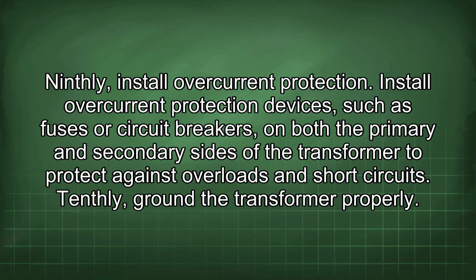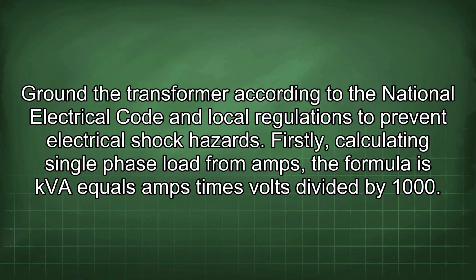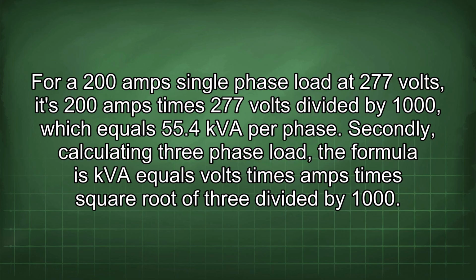Tenthly, ground the transformer properly. Ground the transformer according to the National Electrical Code and local regulations to prevent electrical shock hazards. Firstly, calculating single-phase load from amps. The formula is kVA equals amps times volts divided by 1000. For a 200 amp single-phase load at 277 volts, it is 200 amps times 277 volts divided by 1000, which equals 55.4 kVA per phase.